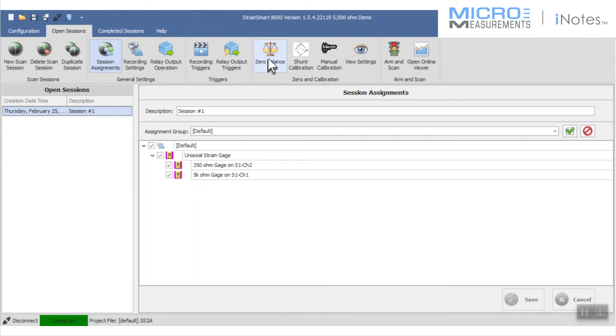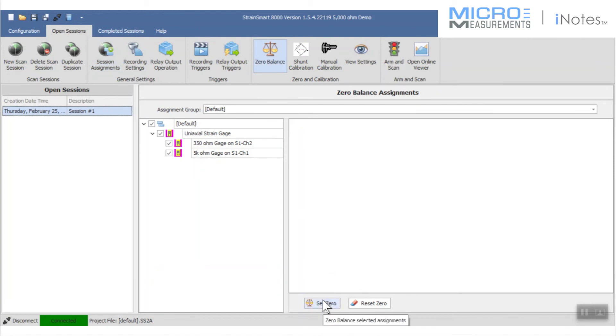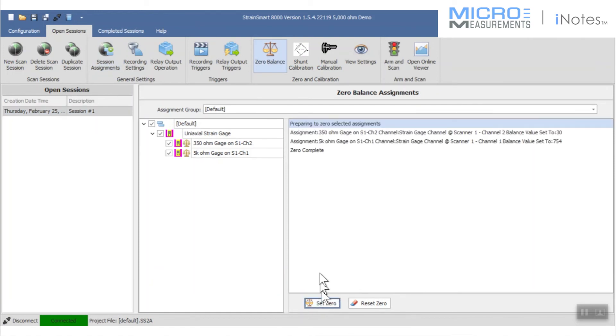When I go to check out functionally my strain gauges, the first step I want to do typically is ask the strain gauges to zero. The system with one quick push of a button here has gone and balanced out each of the channels. There's no errors reported.